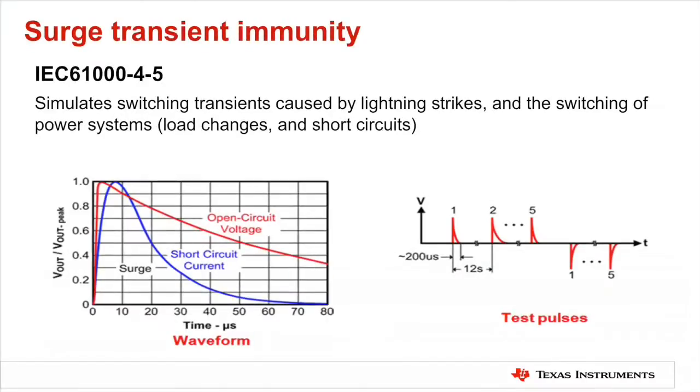While the surge immunity test, IEC 61000-4-5, is the most severe transient immunity test in terms of current and duration, its application is often limited to long signal and power lines of length greater than 30 meters, and high voltage systems that output or input greater than 60 volts. This test simulates switching transients caused by everyday lightning strikes or the switching of power systems, including load changes and short circuits. Characteristics for this test are the high current due to low generator output impedance, and the long pulse duration — approximately 1000 times longer than for ESD and burst tests — indicating a very high energy pulse.